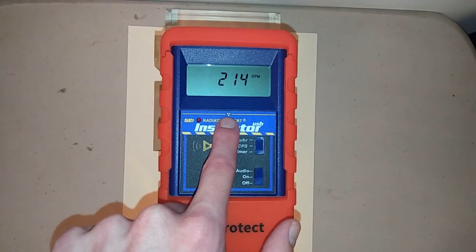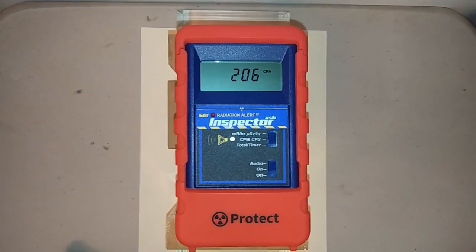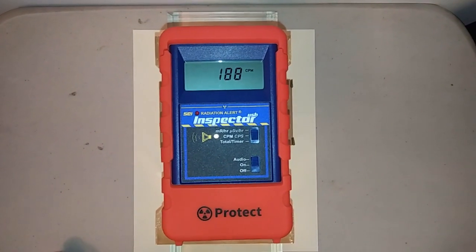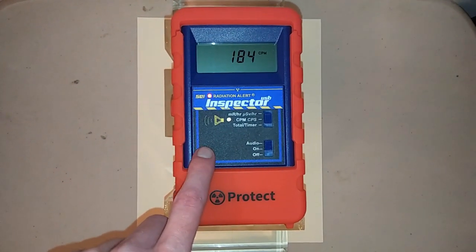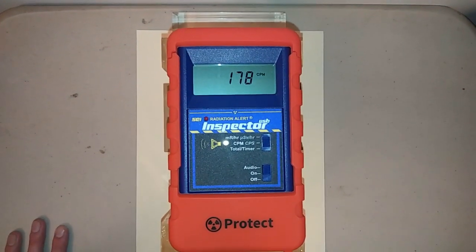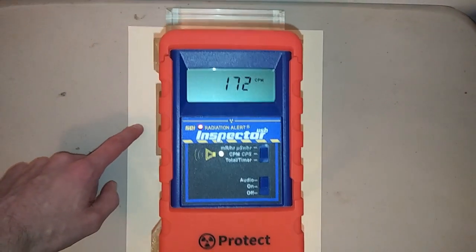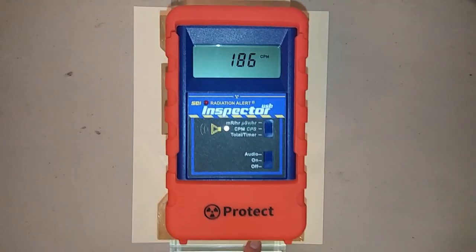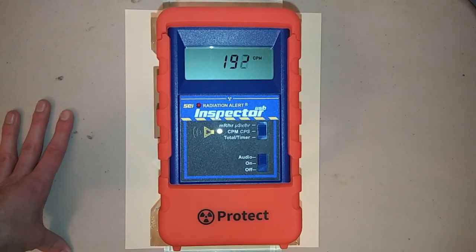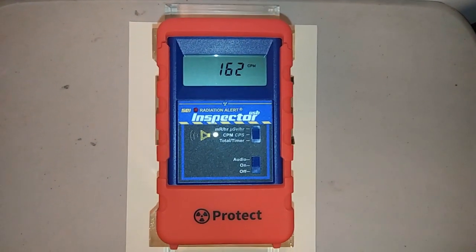The radioactive trefoil here represents the center of the Geiger-Müller detector, which is very useful. Geometry is very important if you're measuring or counting sources. This also has pre-programmable efficiencies built into it too, and you can change those with the Observer software, which is very useful. I have some lines here on this piece of paper to signify where the center of the detector is. And then underneath there is a circle that's the same size as the GM tube. So you get a nice geometry when you're measuring sources.